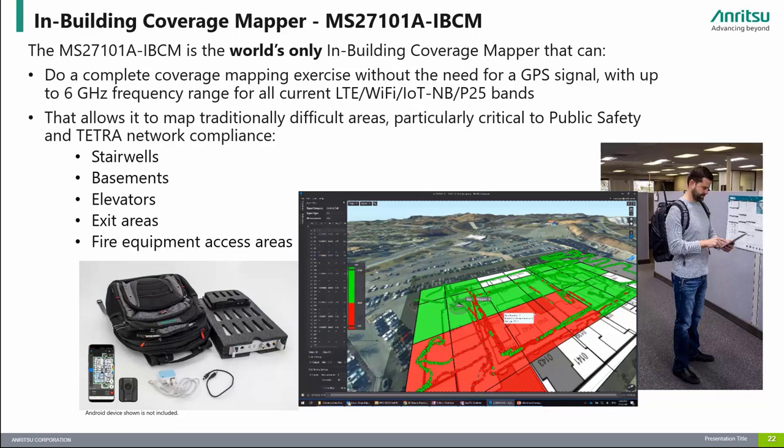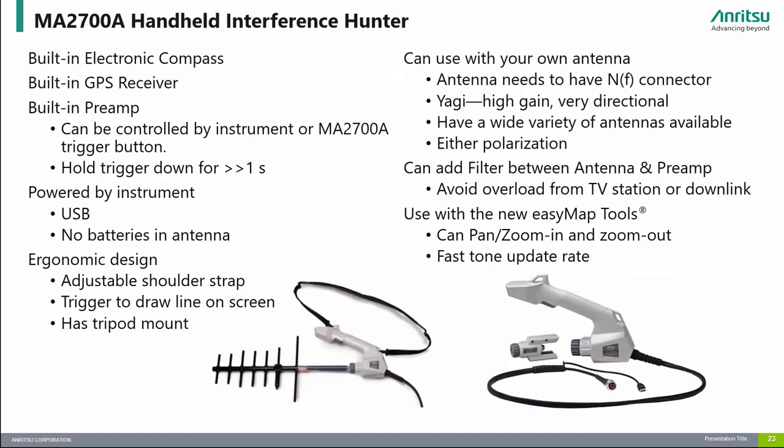Please note that the system requires an Android device which is not included. The MA2700A handheld interference hunter is equipped with a GPS receiver and antenna, an electronic compass, and a pre-amplifier. The internal pre-amplifier can be toggled on or off with the trigger on the MA2700A by holding the trigger for 2 seconds or pressing a button on the attached instrument. It is designed to enhance interference mapping on Anritsu's handheld instruments that have interference analysis options. The MA2700A is powered over USB so it doesn't need a battery, and it requires a compatible directional antenna with easily installed filters.